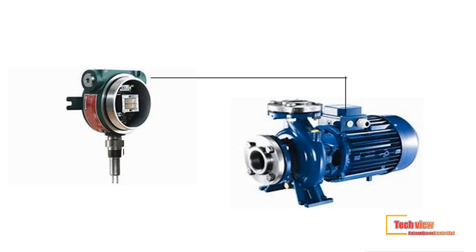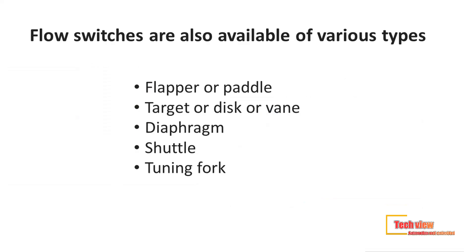Flow switches are devices that monitor the flow through a channel and send a trip signal to various devices in the system, such as pumps. The pump can be indicated by the flow switch to shut down or turn on. Some of the general uses are for the protection of the pump, protection of the cooling circuit, and alarms for flow rates that are too high or too low.